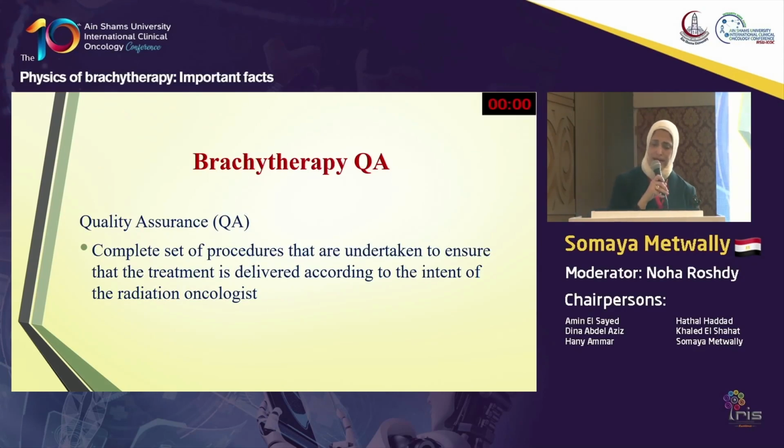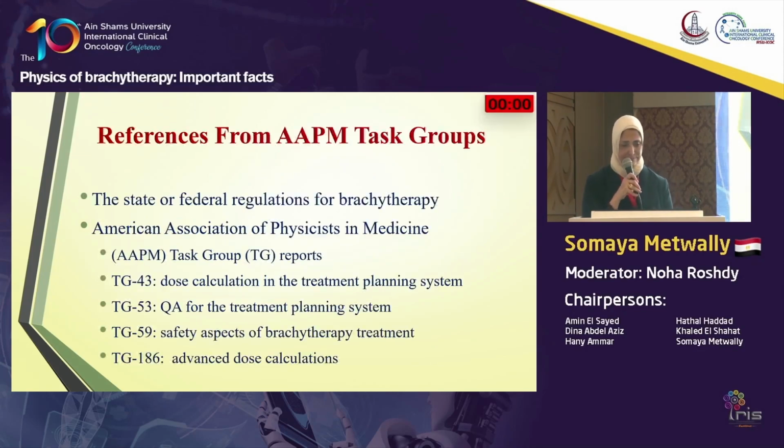So now, brachytherapy quality assurance is a very, very important task. Quality assurance for brachytherapy machines is considered a complete set of procedures that are undertaken to ensure that the treatment is delivered according to the intent of the radiation oncologist, to deliver your prescribed dose as the oncologist described.